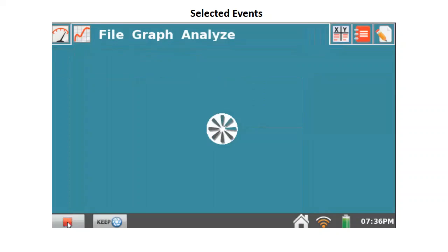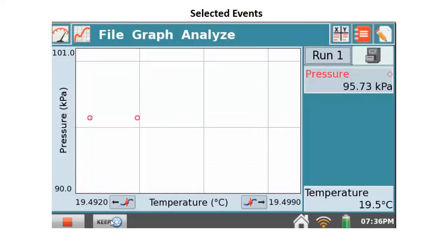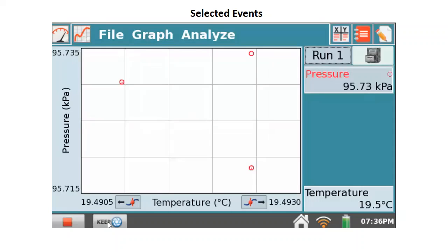Now in selected events mode, you'll see a little point bouncing around — that's the pressure and temperature at this point in time. If you hit the keep button, it will automatically keep that point, keeping both the pressure and temperature values. Unlike events with entry where you have to enter data, here it just takes whatever point that is. So as you go along — imagine your water bath is heating up, pressure is going up — you click keep and there's another point kept. You can take 10 or 15 data points like that and have a pretty good, relatively small set of data to work with.